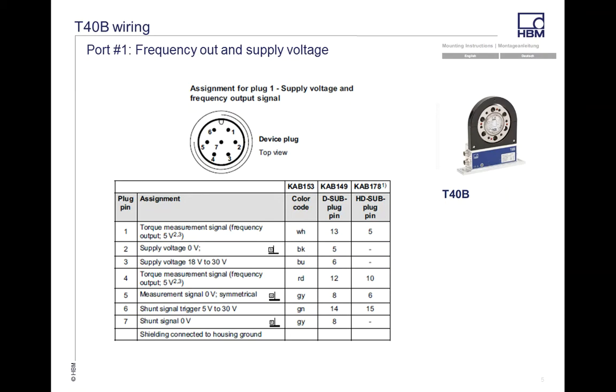Out of Port 1 is your frequency output, set up on pins 1 and 4. The supply voltage goes to the transducer itself. On pins 6 and 7 you can get a shunt. We always suggest using a separate supply for the shunt — that gives you better results and helps avoid any grounding loop issues. All of this is covered in the manuals, which you can download right off our website.